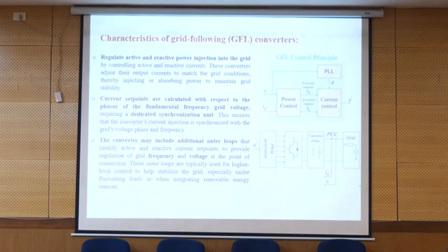I mentioned that we have 1 megawatt active power and 50 kilowatt reactive. It means that the converter is responsible for injecting that much, because the set point is for that. Mainly this happens when we are in power plants. It is very important to consider that. So, any questions so far?